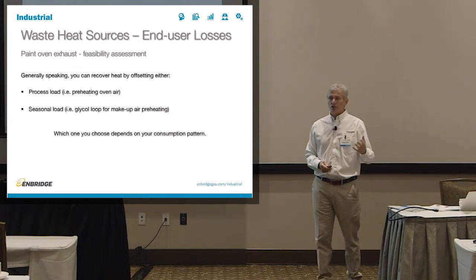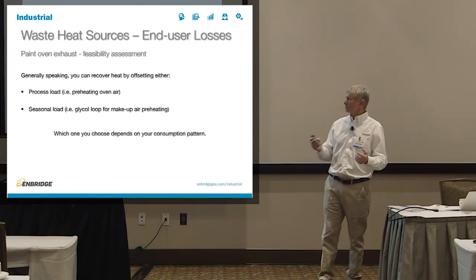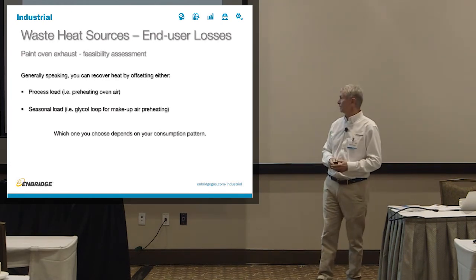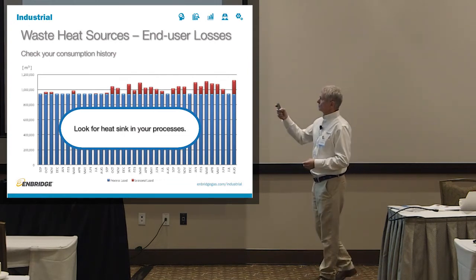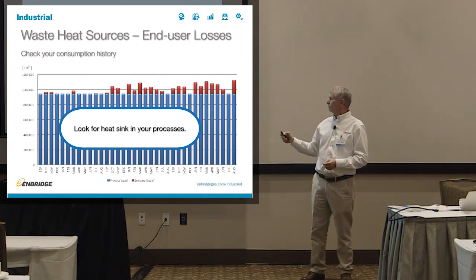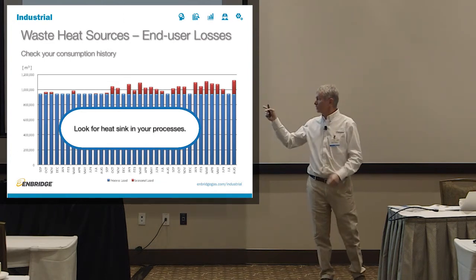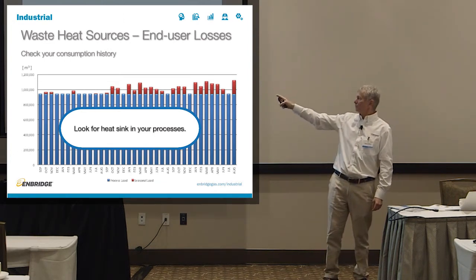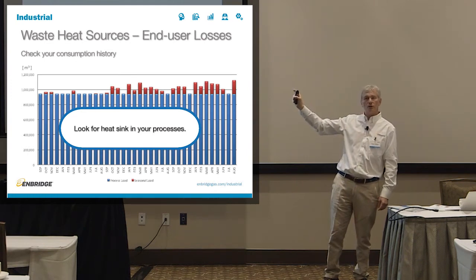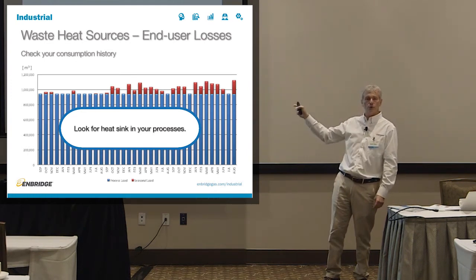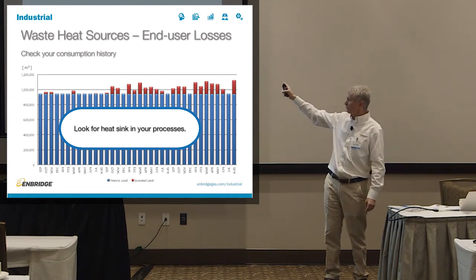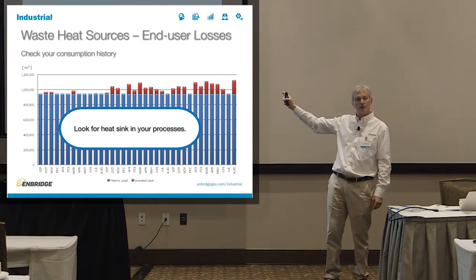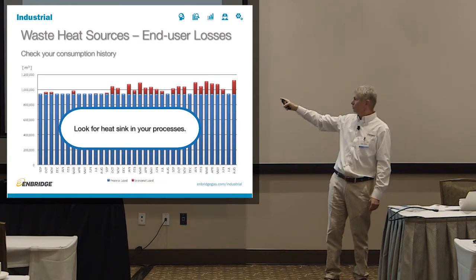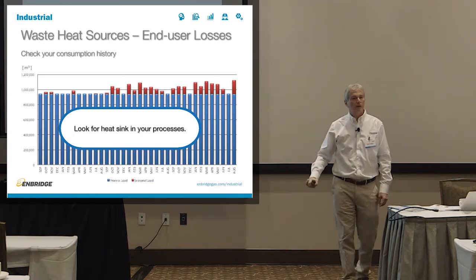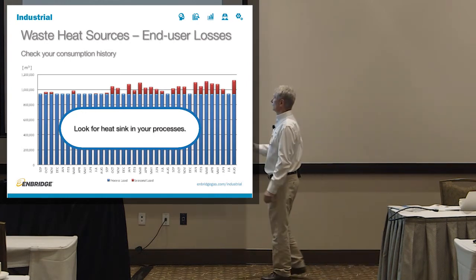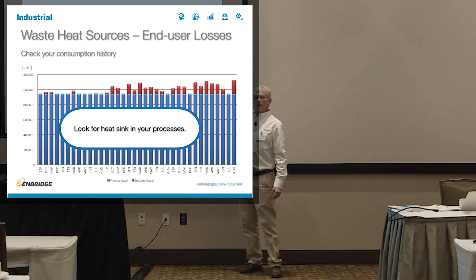We already talked about this: process load or heating load, seasonal load. Which one you choose depends completely on your consumption pattern. I'm not going to go into this because we do this a lot, but you should really look at it. If you look at the last 3 years of your natural gas, and our ESCs can do this for you, and you have a lot of blue bars, which means a lot of process heat, see how the load is steady regardless of whether it's January or July? You want to look for the heat sink in your process. You wouldn't believe how many people will come with this profile and want to recover it in the seasonal load.